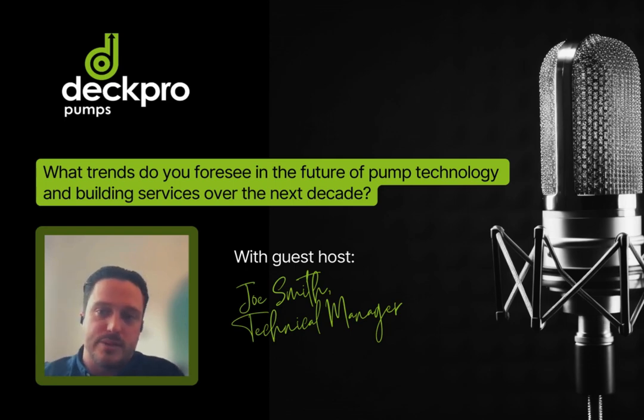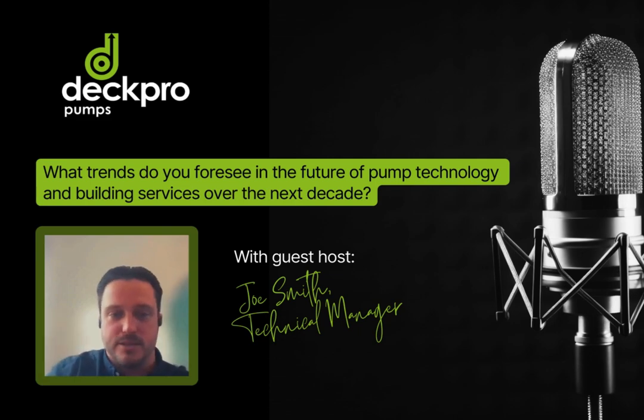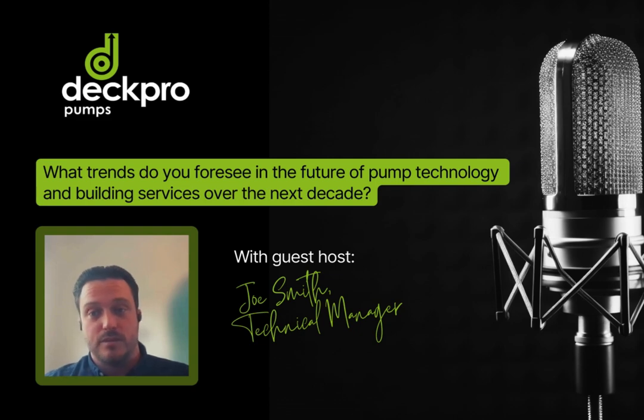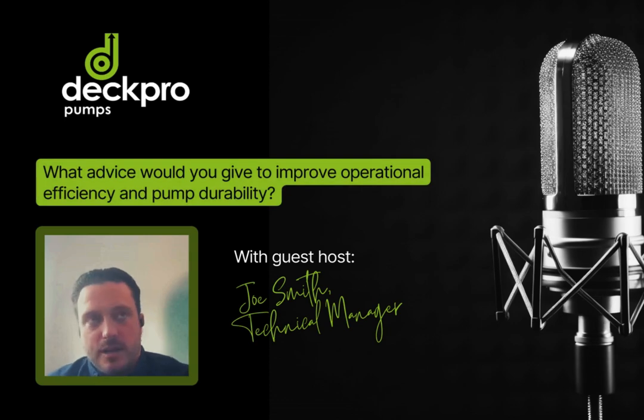I wonder if one day we're going to start seeing some of that come back into the pump industry, because the whole world is going all electric. It kind of means electric motors are already ahead at the moment, but there's a lot more innovation that can be done. One thing is, if you walk into a plant room, you'll often see in the summer a chiller system where you've got two big chiller pumps, or one big chiller pump, depending on how big the building is, and they'll be running at full capacity.